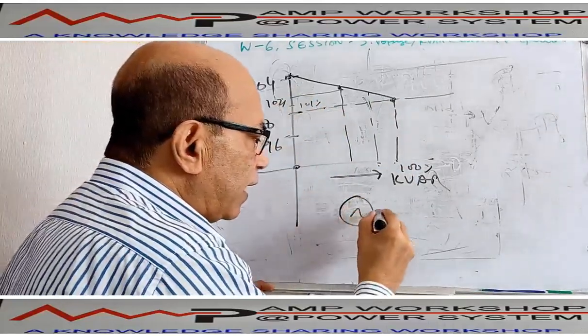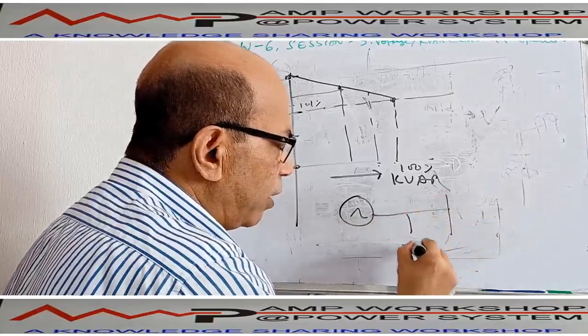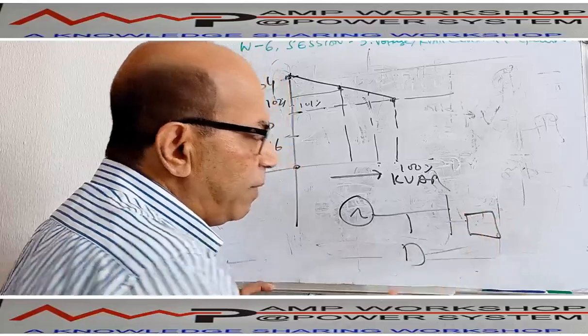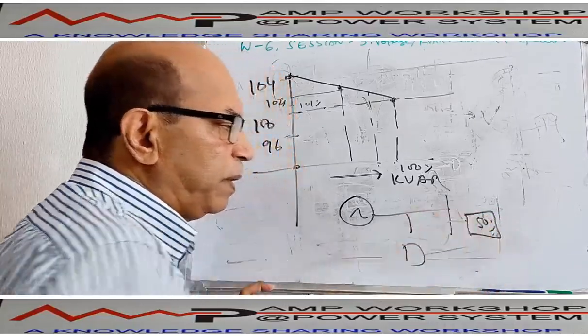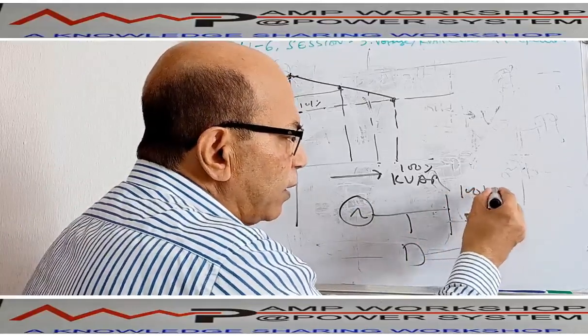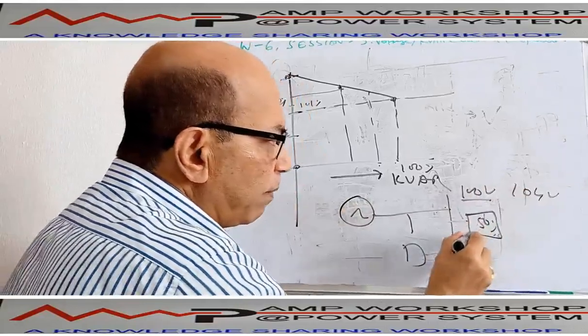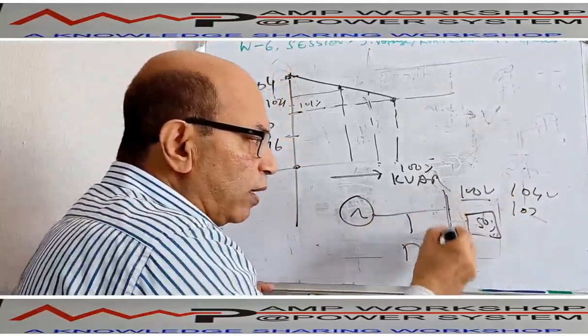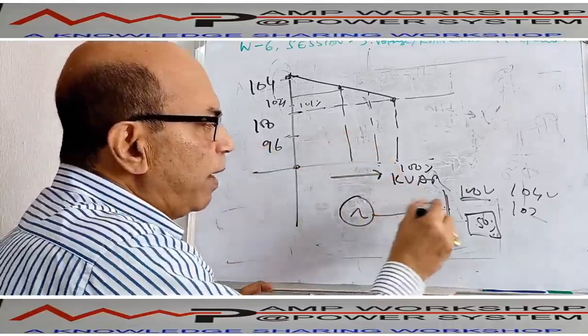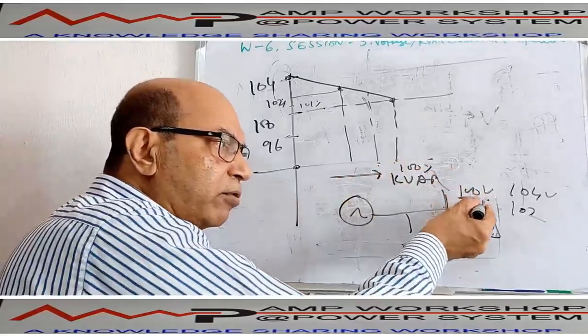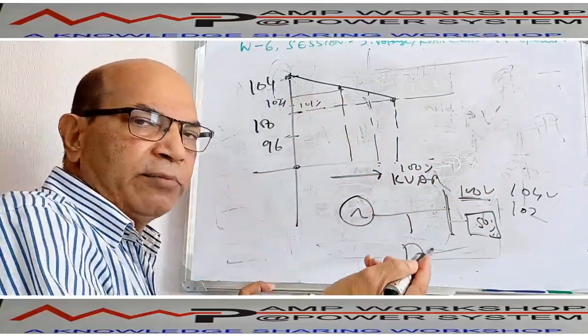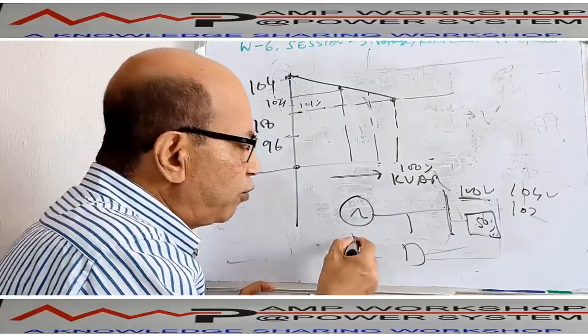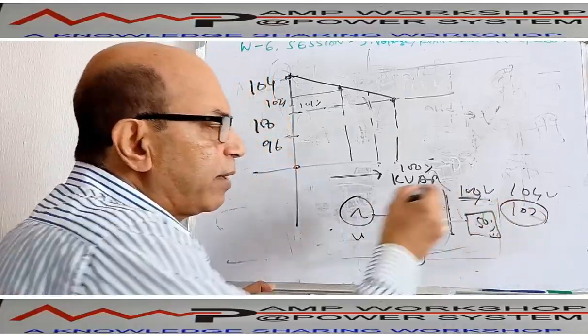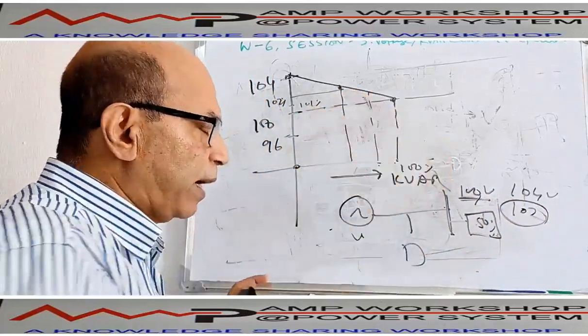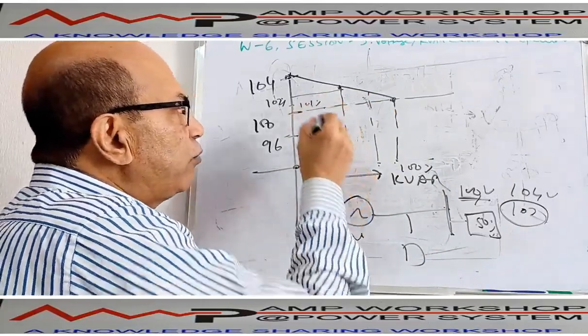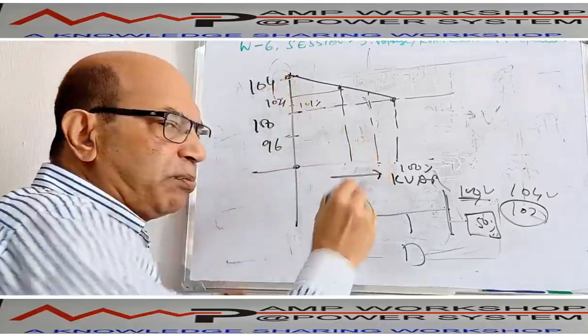Suppose this is a generator running in droop mode. This is a bus, and you are sensing the voltage from here to the governor. Now, when you are loading this generator, suppose you load 50% KVAR, and suppose it is a 100 volt bus. At zero load it was running at 104 volt. When you load 50%, the voltage will come to 102 volt. But your bus voltage is 100 volt. If you leave the machine that way, the voltage will be 102 volt instead of 100 volt. So if you want to bring it back to 100 volt, you have to intervene manually, with a manual switch. With the manual switch, you reduce the excitation so that it comes down from 102 volt to 100 volt. It is the same as a speed controller. So this is the droop characteristic. But in this characteristic, how much load the machine takes depends on the speed. As per the speed, it will take the load.